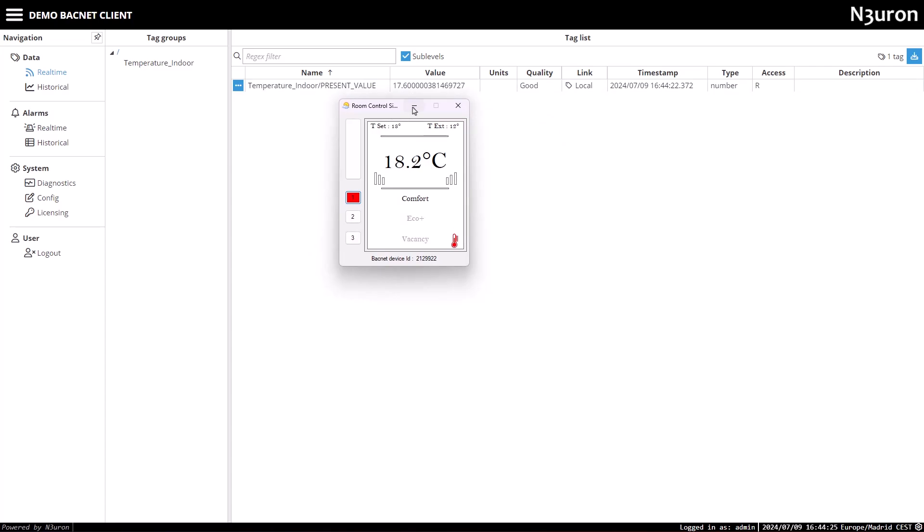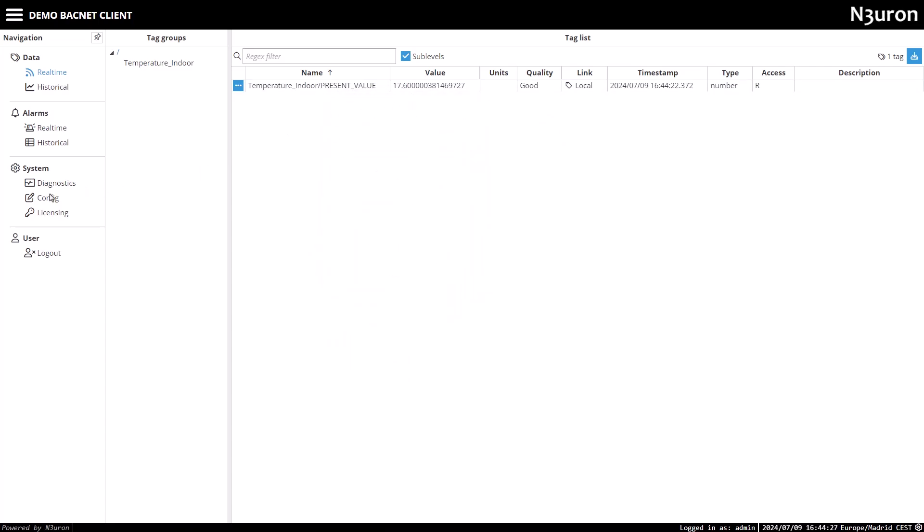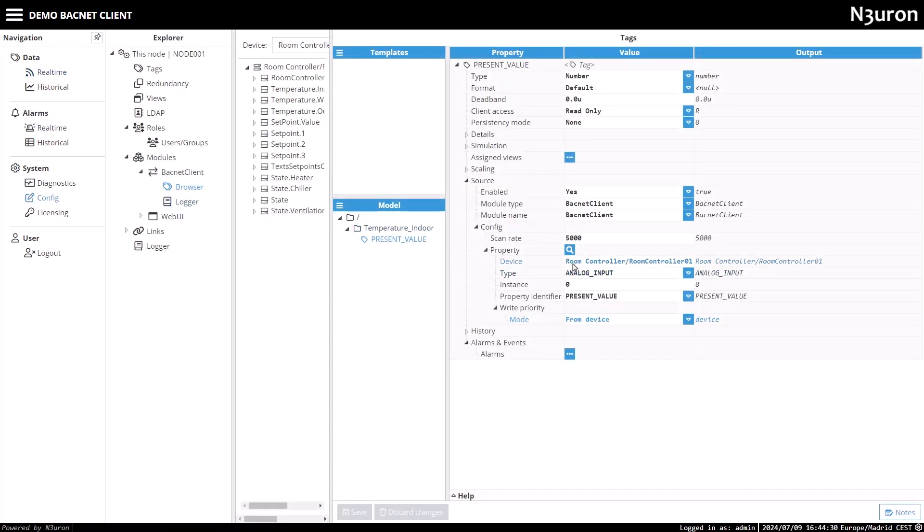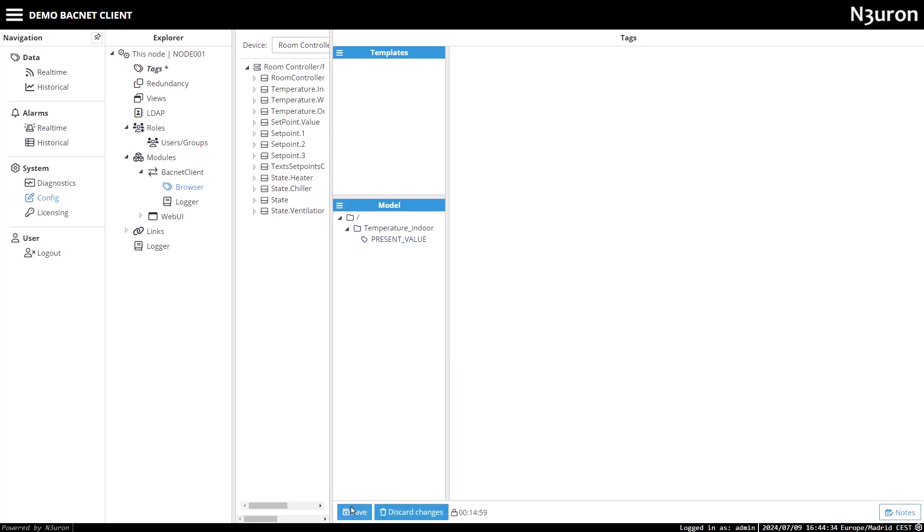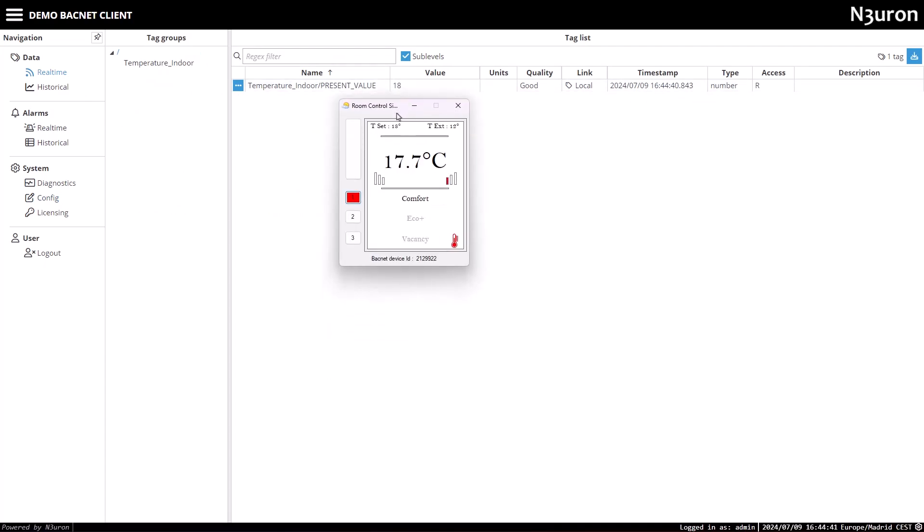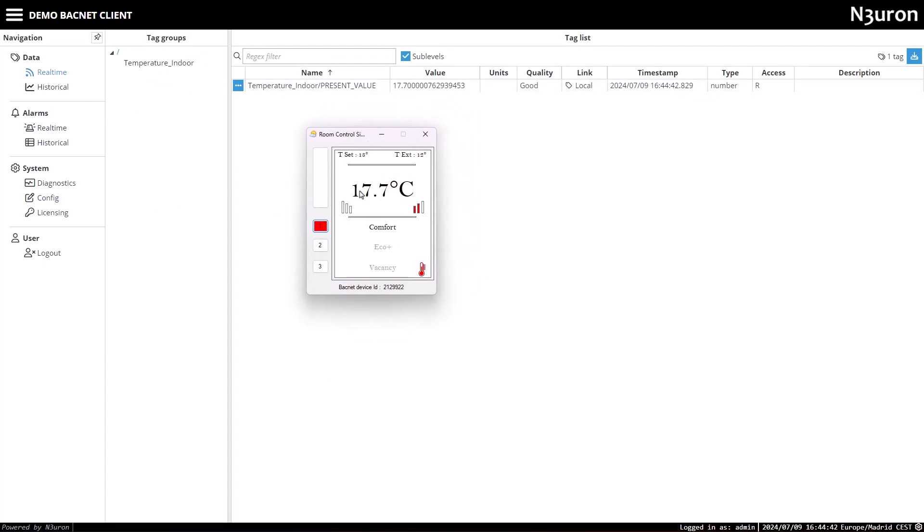To address this, I'll adjust the scan rate until the readings are more timely. I could also set a deadband in the tag configuration to only update the tag with significant changes in the actual value, but I'll leave it as default for now.